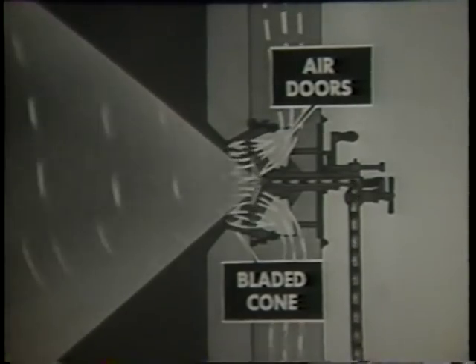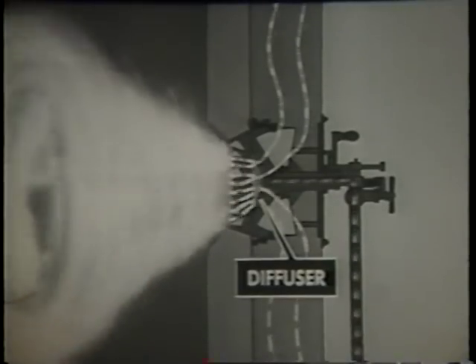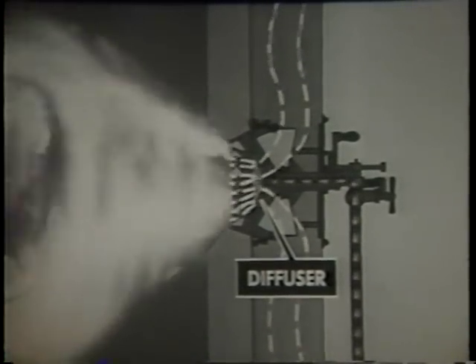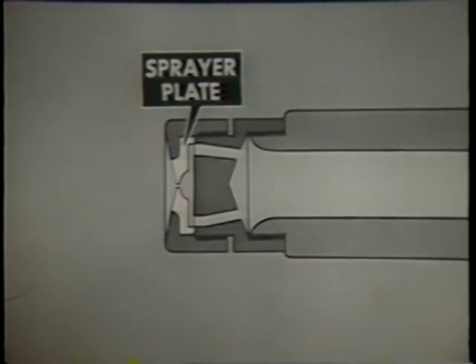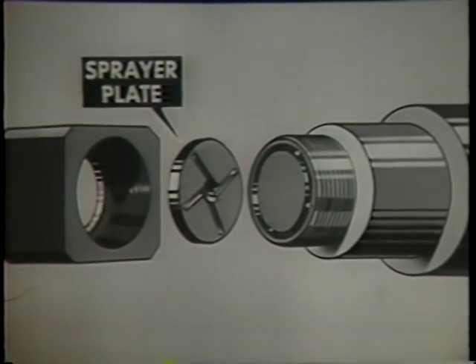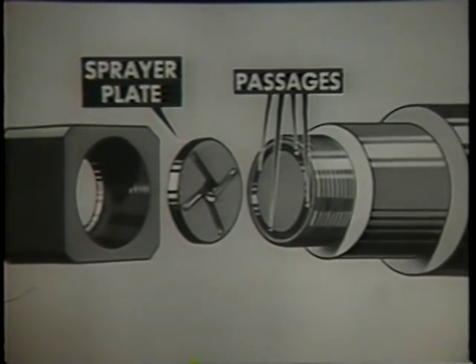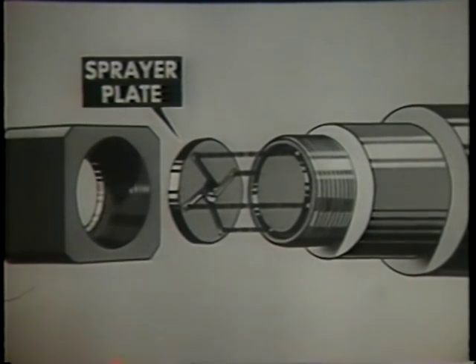Meantime, in the burner register, air provided by the forced draft blower is given a rapid rotating motion by the air doors and bladed cone and mixed with the oil spray. The mixture of oil and air enters the furnace where combustion takes place. The diffuser prevents the air blast from blowing the flame from the atomizer tip. In an exploded view, you can see how the oil passages in the atomizer nozzle guide the oil into the slots of the sprayer plate, how the slots give the oil a very rapid whirling motion in the whirling chamber, and how the whirling oil emerges from the sprayer plate orifice as a hollow cone of mist-like oil particles.